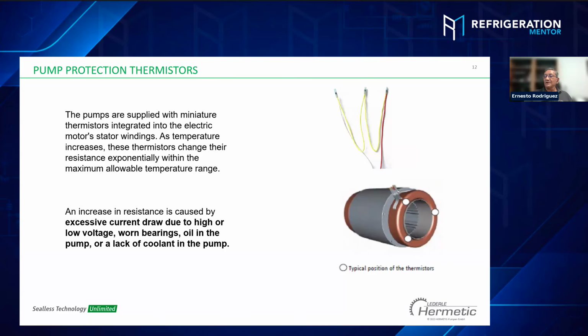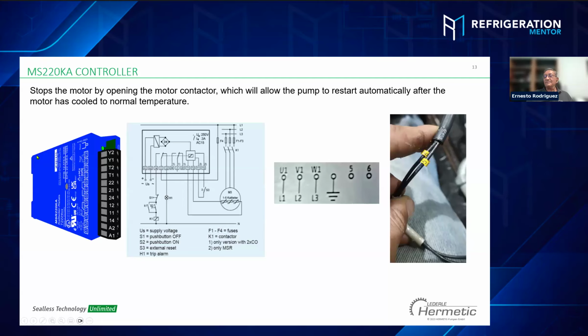All hermetic pumps come with thermistors. The thermistors are a device to protect the winding of the motor from overheating. When the temperature increases, the thermistor is going to open and shut off the pump. Basically, we can use a controller. We have a type of controller. Some companies use PLCs to connect the thermistors, or we can separately offer this controller. This controller is able to stop the pump when it's overheated. We have the wiring diagram right here, which is for 220 or 440, plus ground, plus cables 5 and 6, which are the ones to connect to the controller. We have T1 and T2, which is where the thermistors need to be connected. If anything increases the temperature on the winding, the pump is going to stop immediately to prevent any damage to the motor.